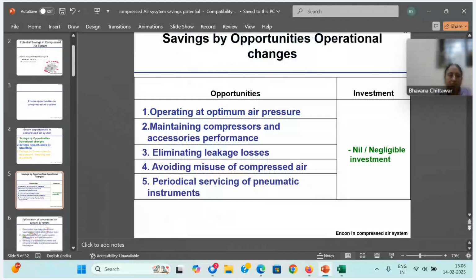Operating at optimum air pressure. You operate the compressors only at the required air pressure. Often I find most industries operate at a much higher pressure than required. So you have to give a minimum allowance or cushion in the compressor operating pressure setting. You have to investigate in total, starting from the application in reverse. You cannot just reduce the pressure at the compressor and achieve the savings. You have to see each and every application; every application will have its own pressure regulators. Some regulators would be kept at 4.5, some at 5.5, some at 7 kg. So you have to study in total, and only then can you optimize air pressure.